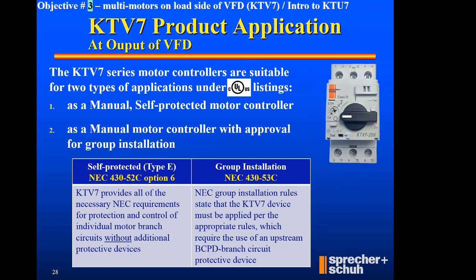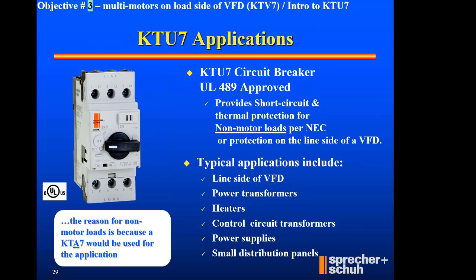And how are we doing that again? KTV indeed complies with self-protected type E, and we're using 430.52(C)(6). KTV provides all the necessary requirements for protection and control of an individual motor without additional protective devices. So it's either a self-protected motor controller, or we're applying group motor rules. Group motor rules meaning I'm going to have additional protection upstream of that. So on the right side, group installation 430.53(C), installation rules state that the KTV7 device must be applied per the appropriate rules, which require upstream BCPD. So that's how a KTV is able to do the job on the load side of a VFD in a multiple motor situation.